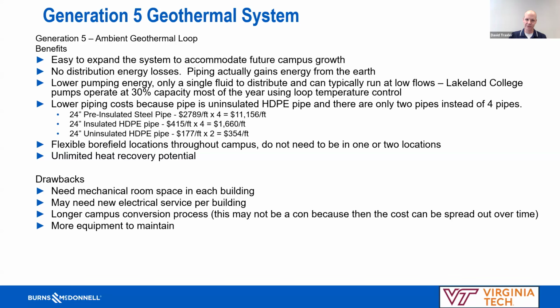And that's what we saw, where the buildings were much further apart. You had a lot more piping. It just made sense to go with the ambient loop network. One thing you have to be really aware of, though, when you go ambient loop, is you have to have utilities and space in the building. You need mechanical room space. You probably are going to need to upgrade your electrical service to your building, or at least do some significant electrical work. You're going to have longer campus conversion processes, which may not be such a bad thing. Like Colorado Mesa, just like Carrie said, has been doing this since 2007. So it helps if you're doing it over time with your capital budget and expenditures of your campus. It's a little bit more equipment to maintain.